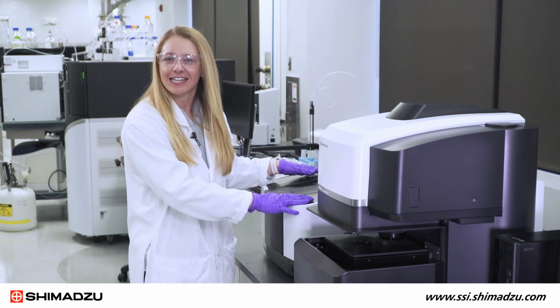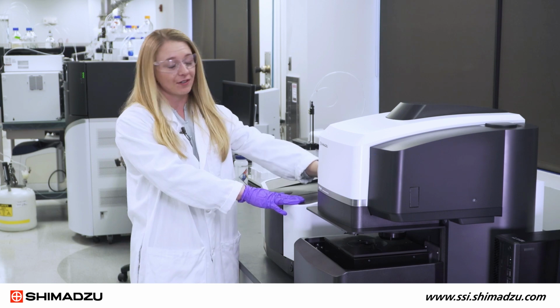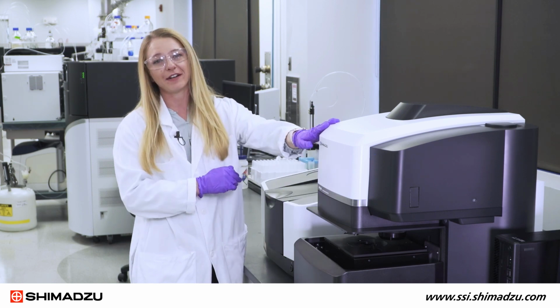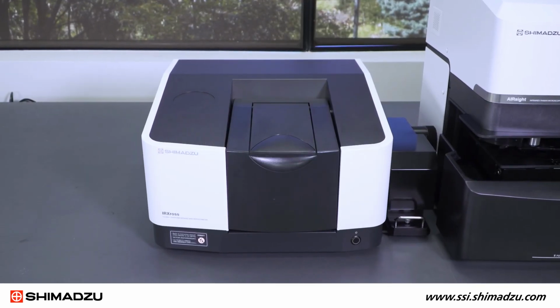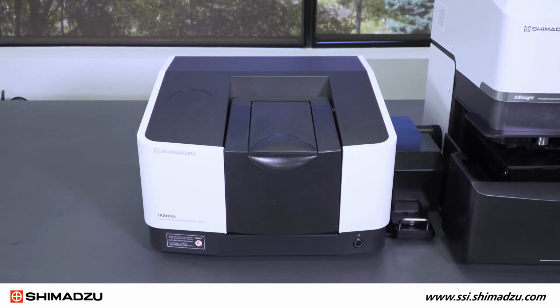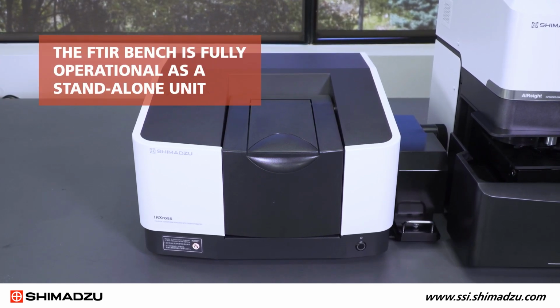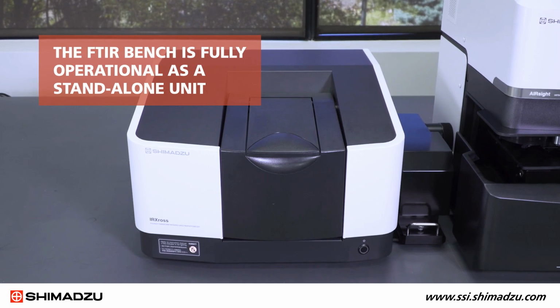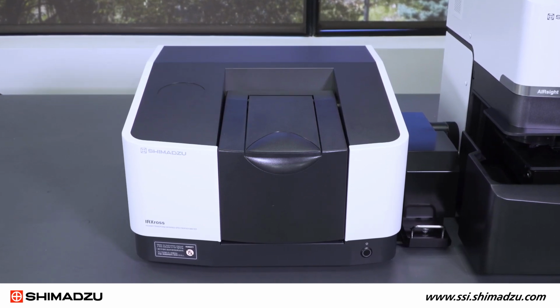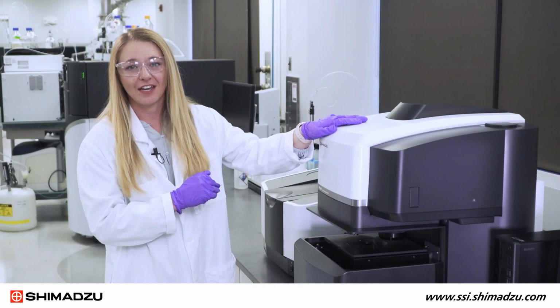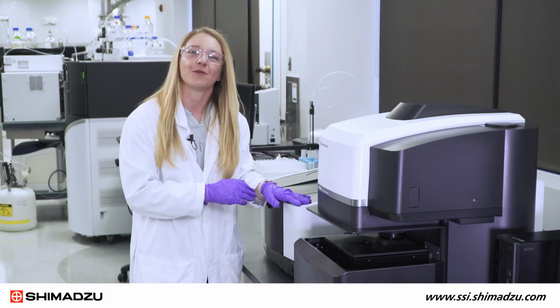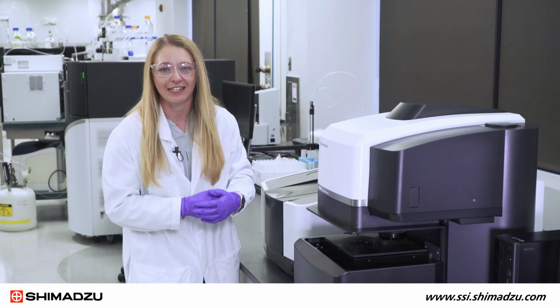On the left side is the FTIR bench, which is used as the infrared source and interferometer for the IR microscope. Here I have the IRXross spectrometer. You may have a different model, but in principle, it's the same. The FTIR bench is fully operational as a standalone unit, even if it's physically connected to the microscope. If you'd like to know more about using your FTIR bench, then check out my FTIR Best Practices YouTube video on our channel.